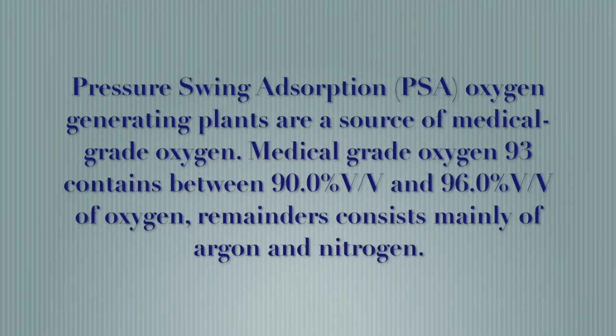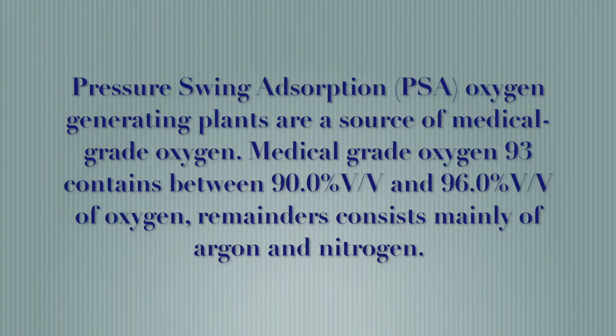The pressure swing adsorption plants are a source of medical grade oxygen. The medical grade oxygen, 93, contains between 90 to 96% volume by volume of oxygen; the remainder of the gases consists mainly of argon and nitrogen.